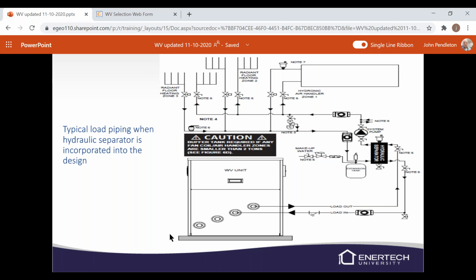And so if you need 5 GPM going through the unit, and the zone that you have only needs 3 GPM, you're going to flow into the hydraulic separator, and you're going to pull back out of the hydraulic separator to the unit. So the unit's still going to pull that GPM that it needs. And then the zone is going to pull from the hydraulic separator the flow that it needs. The hydraulic separator will also capture any dirt or debris, and there's a blowdown valve on the bottom of it. It will also collect any air and will vent that air out through the air vent on top of it.